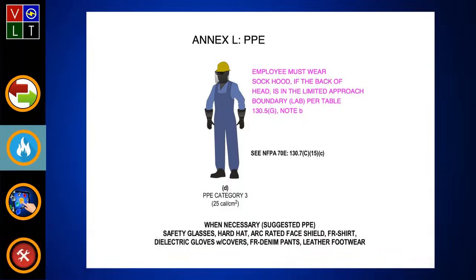Welcome, Mike. Now again, this is Category 3 - in other words, you're over 8 cal up to 25 cal. You can wear the sock hood the individual has on and dress like that up to 12 cal. Once you're above 12 cal, then you'd have to go into the moon suit.